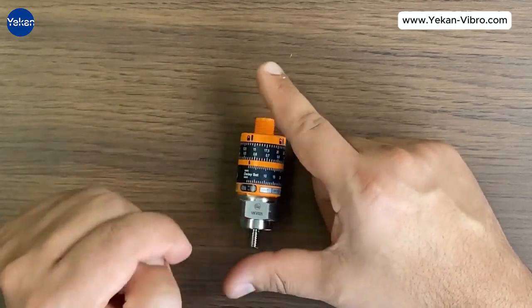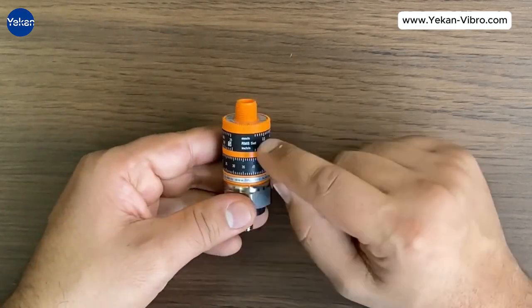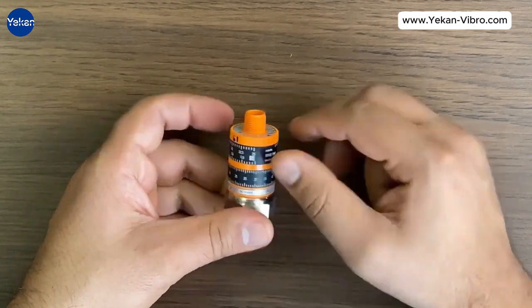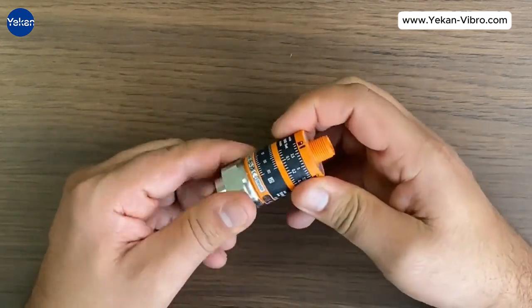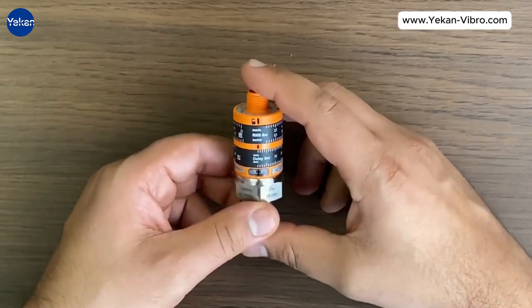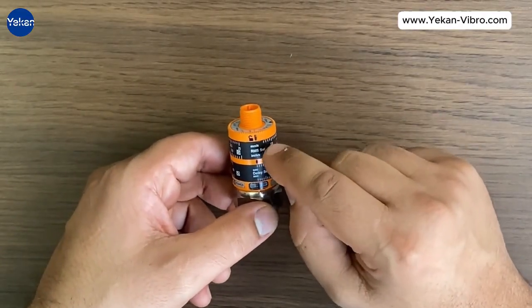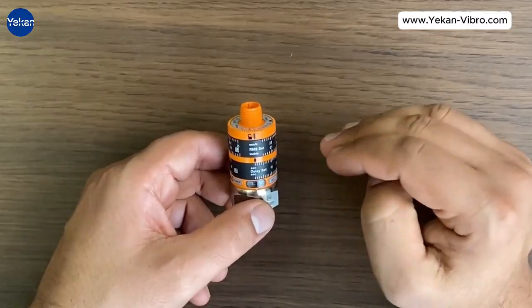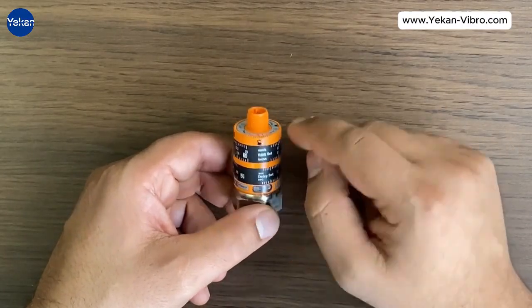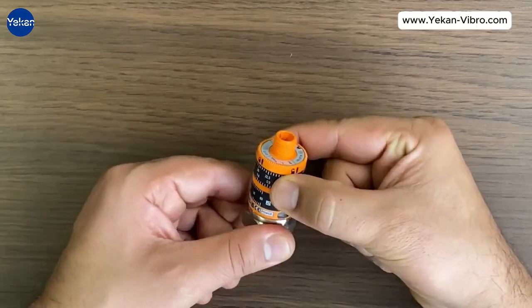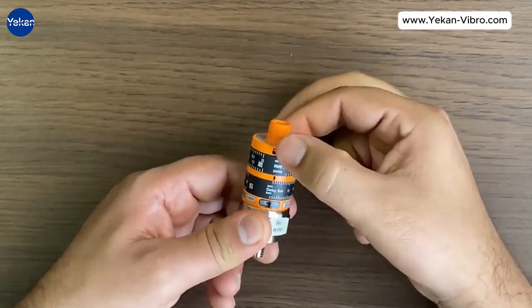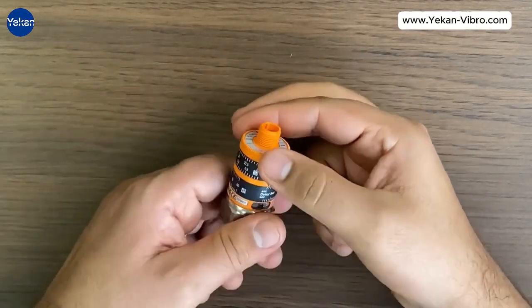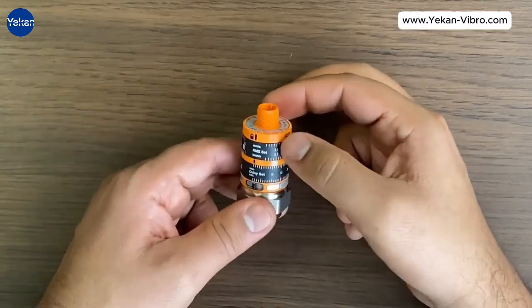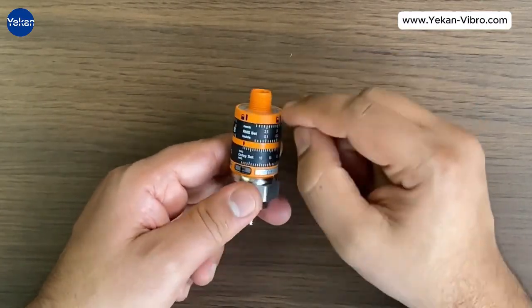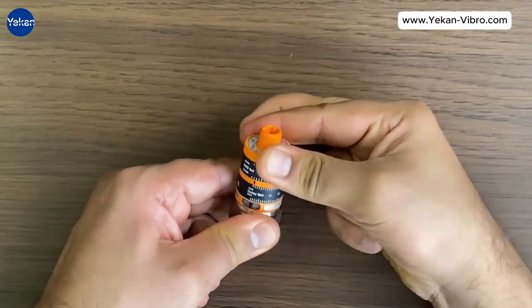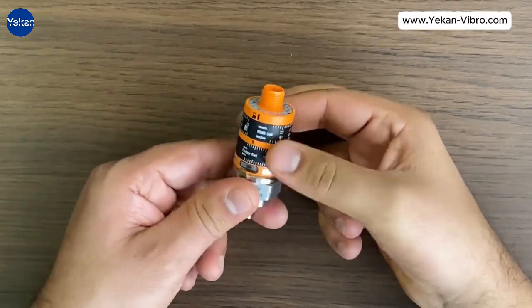Here we see 2 adjustable parts. One is for the set point and the other is for delay. Let me explain these. There are 2 movable elements. The first one adjusts the set point, the vibration threshold at which the relay activates. The second one is for delay. To adjust them, first unlock the mechanism. When the sensor is installed on site, you should keep it locked to avoid accidental changes. To unlock, grab the top part and turn it until it aligns with the arrow, then it becomes movable.